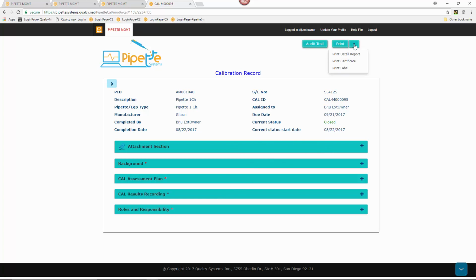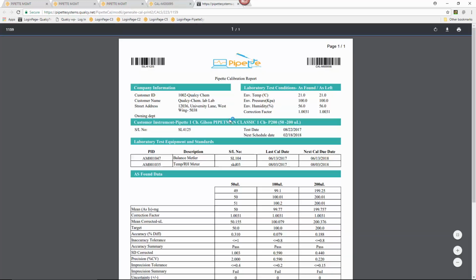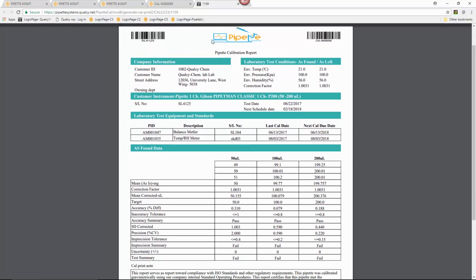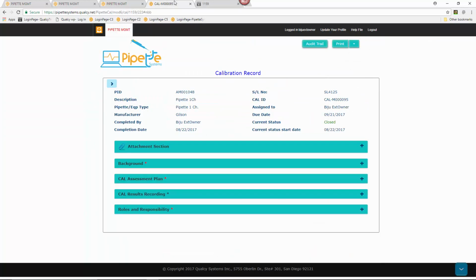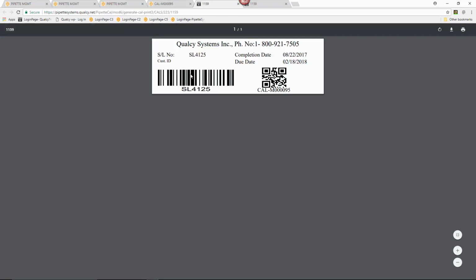So at this point I can print out my calibration certificate. As you can see, the system has already calculated the accuracy and precision and created a calibration report. And also I can go to the calibration record and print a label that I can use on my pipette. And this also provides me the option to track when the next due date for the pipette calibration is.